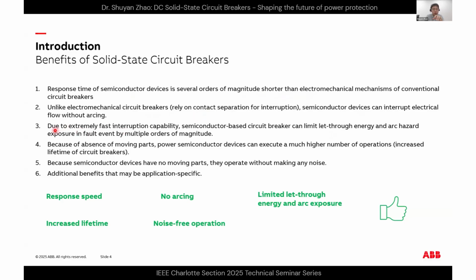Third, due to the extremely fast interruption capability, semiconductor-based circuit breakers can effectively limit the let-through energy and hence the arc hazard exposure in a fault event, by multiple orders of magnitude compared to traditional electromechanical technology.